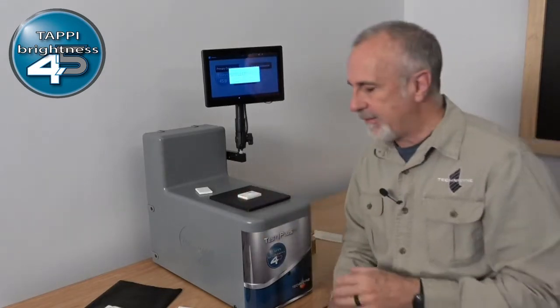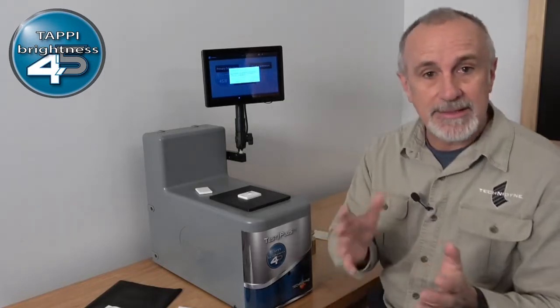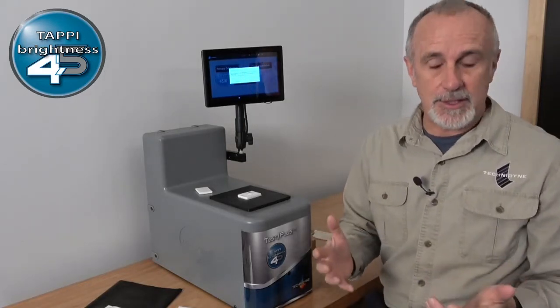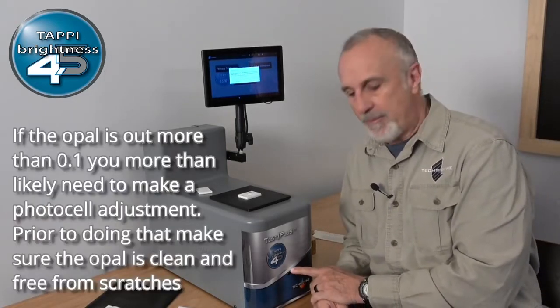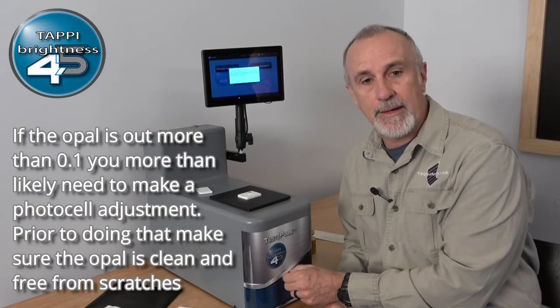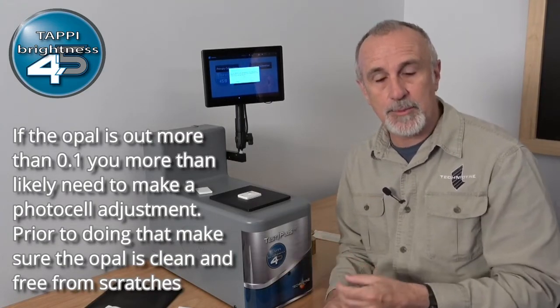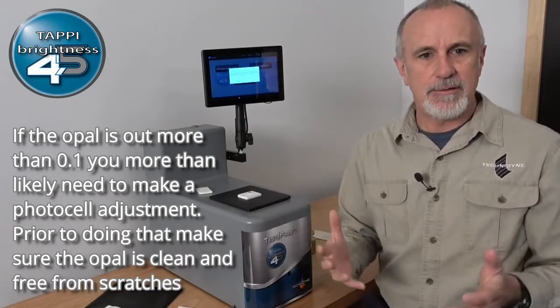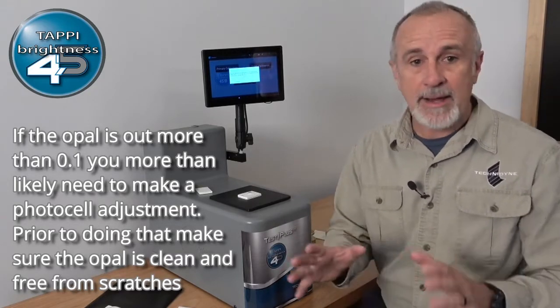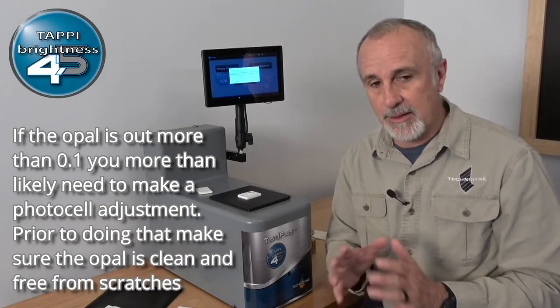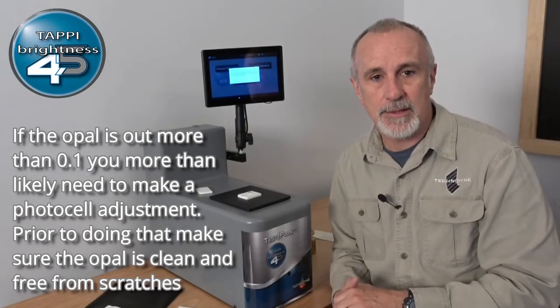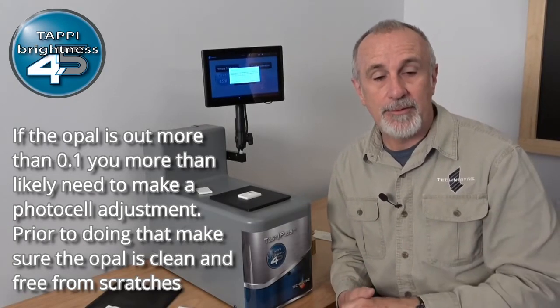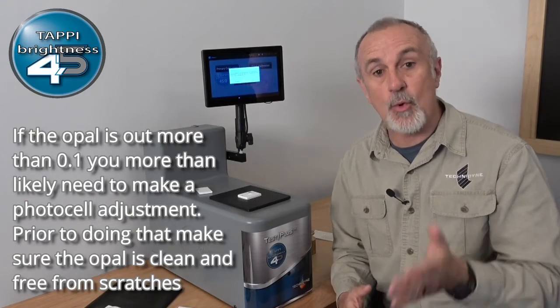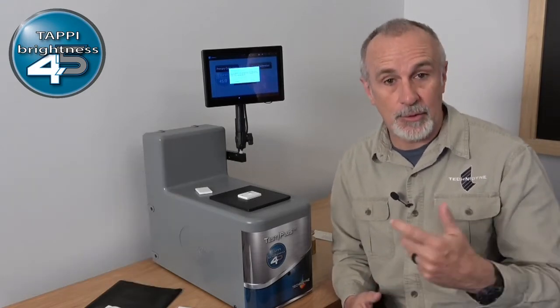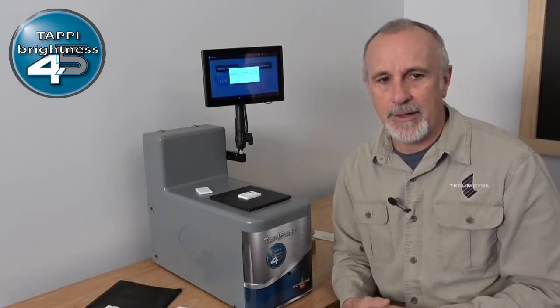Let me stop for a second. If for some reason that is not within a tenth, you have to make a photocell adjustment. To do that, you pop this little cap off right here, and that gives you access to the photocell adjustment. With the instrument, you received a photocell adjustment tool. We're not going to go through that process today because that takes a little bit longer than the basic calibration of the instrument, but we'll have a supplemental video which will show you how to step through that process, or you can contact our service department or your local area representative and they can talk you through that step.